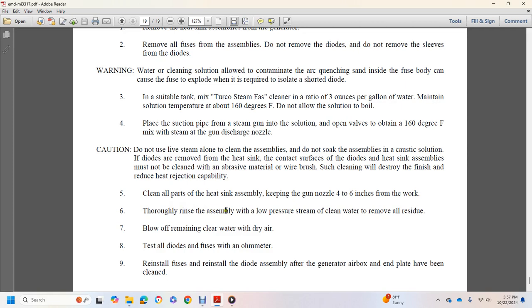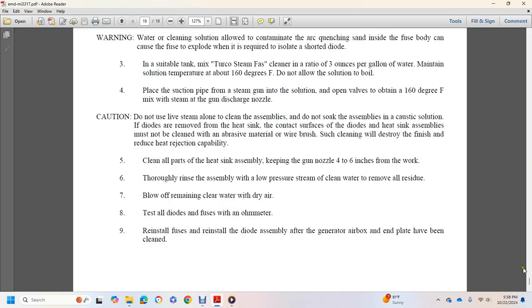6. Thoroughly rinse the assembly with a low pressure stream of clean water. Remove all the residue. 7. Blow off remaining water with clean dry air. 8. Test all diodes and fuses with an ohmmeter. 9. Reinstall the fuse. Install the diode assembly after the generator airbox end plate has been cleaned.